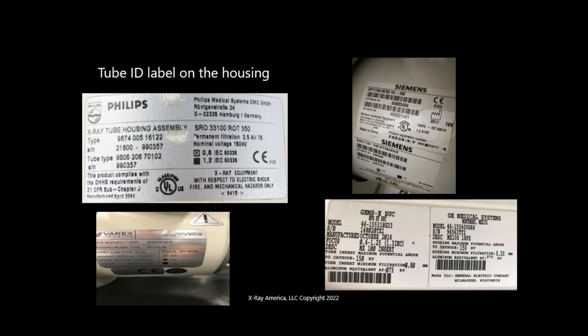And these are labels. When you're trying to buy a tube, this is the information your technician gets from the label. It tells us a lot. It tells us the focal spots. Typically, the part number, the model number, will give somebody who's supplying a tube everything. Interesting sometimes: the ages of the X-ray tubes. I've seen X-ray tubes come back 30 years old, particularly in a low-use rad system or even a high-use rad system, if it's treated properly.